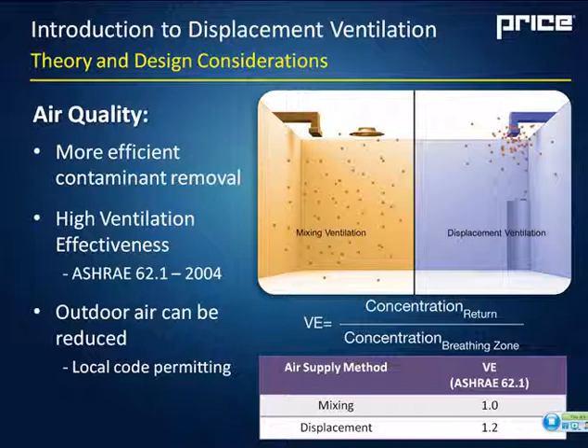ASHRAE 62, the standard for ventilation rate and indoor air quality, actually gives you a ventilation discount. So with a mixed system, the best case that you can get is a ventilation effectiveness of 1, which means the concentration of any contaminant or any measure at the return over the concentration at the breathing zone is equal to 1, meaning the room is entirely mixed, and with a mixed system you really can't do any better than that. Now with the displacement system, because we can stratify those contaminants away from the occupied zone, we can actually get a 20% better ventilation effectiveness.